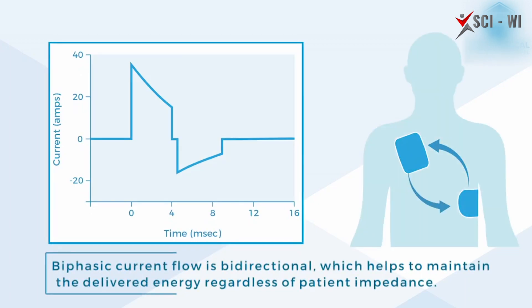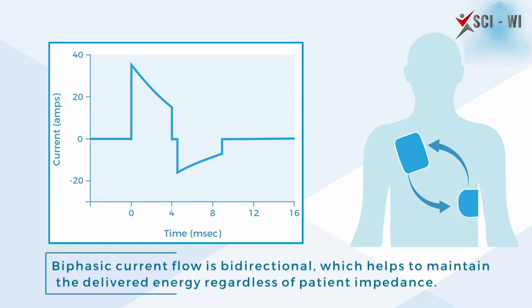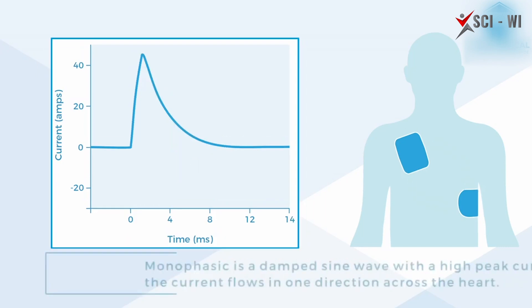In monophasic machines, the delivered current is high, which is why these machines were usually on the bulkier side. However, most manufacturers have ceased the production of monophasic devices and have started producing biphasic devices.